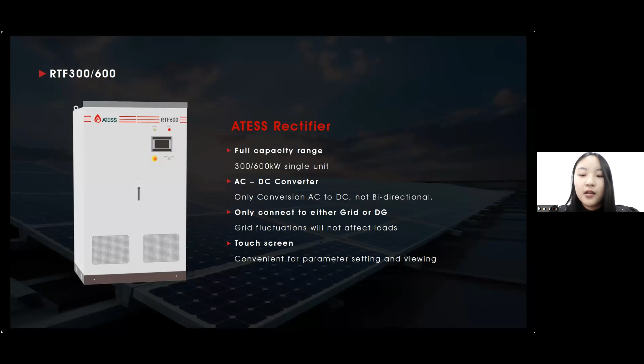That means the power cannot flow back to the grid. And the next page here is a DC coupling system diagram. So let's have a look on the right side. The AC input power converts to DC power output through RTF, and the battery and PV power, they are DC power sources, right? They are coupled on this main DC bus on the bottom and combined by the DC cabinet. Then the power will flow to PCS.